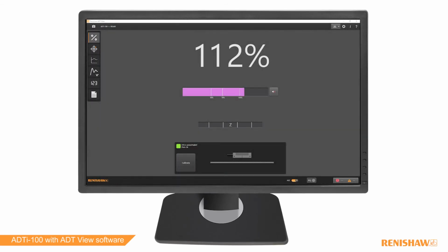The signal screen is used to monitor signal strength during the installation and calibration of the read head and for in-field diagnostics. Use the Calibrate button during installation to initiate the incremental signal calibration and the reference mark phasing.